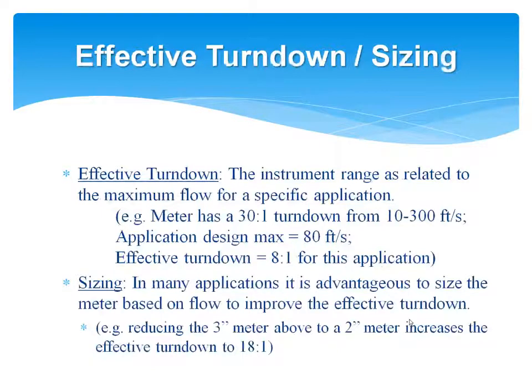What's very, very important when talking about turndown is getting back to the actual effective turndown of the meter for the application. So again, continuing our example, we have a meter that has a 30-to-1 turndown from 10 to 300 feet per second. Well, if the application design maximum is 80 feet per second, that meter is only going to have an 8-to-1 turndown for the application. And that might not be enough if you've got widely varying steam flow rates and you want to be able to measure in partial load situations.